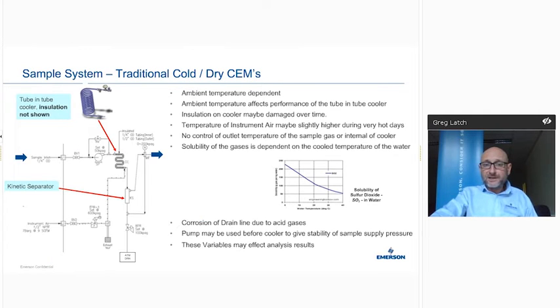Sample systems, just to give you a little brief overlook on traditional, what we call cold, dry system. As we discussed before, you've got your preload sample takeoff point. Ideally, you've probably taken out the majority of your particulates and the likes at an elevated temperature. Close coupled to that, then you have, in this particular case, we're just showing a pump and what we call a heat exchanger, just an air heat exchanger in this particular case. Obviously, some of the challenges in that is depending on your air temperature and open to a hot environment. And again, being close coupled to, dare I say, the point of extraction, you do get a lot of ambient and latent heat, and that can and does affect your efficiency of that heat exchanger.